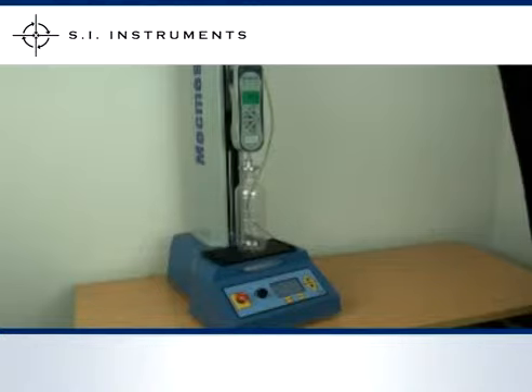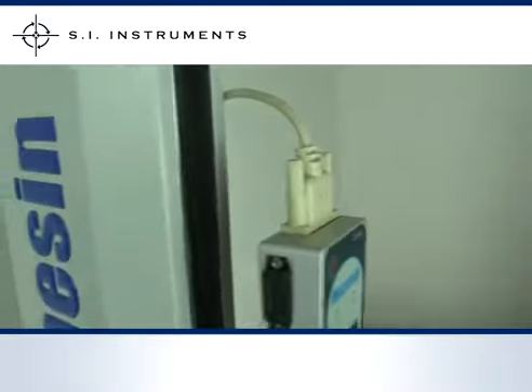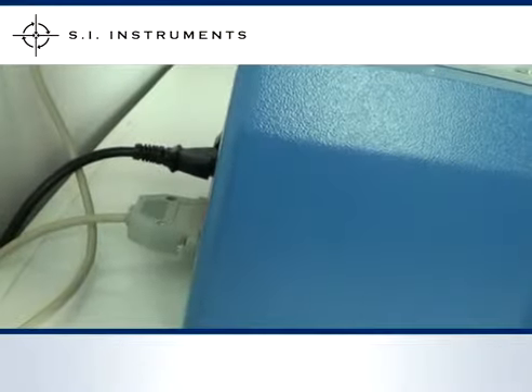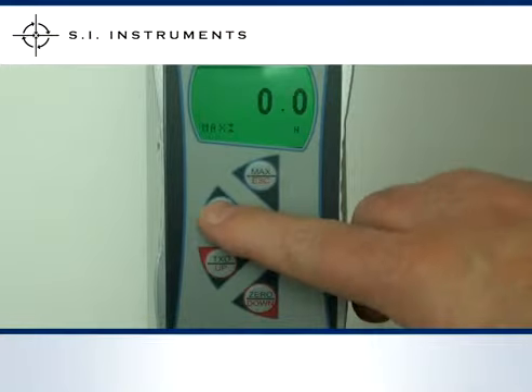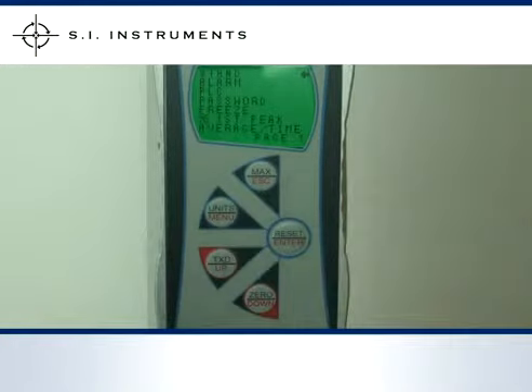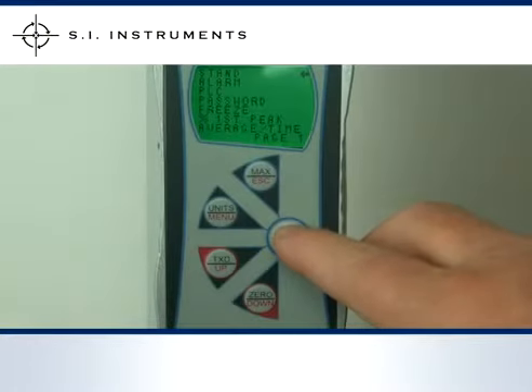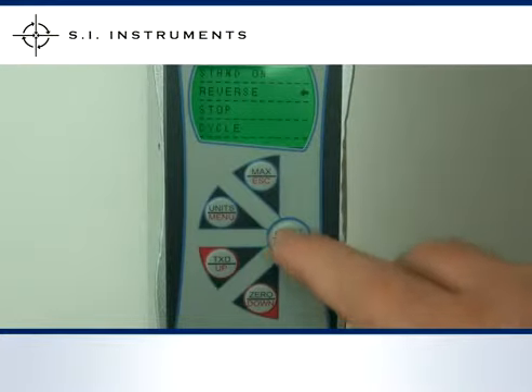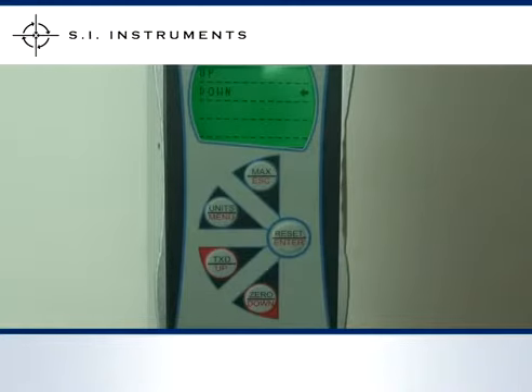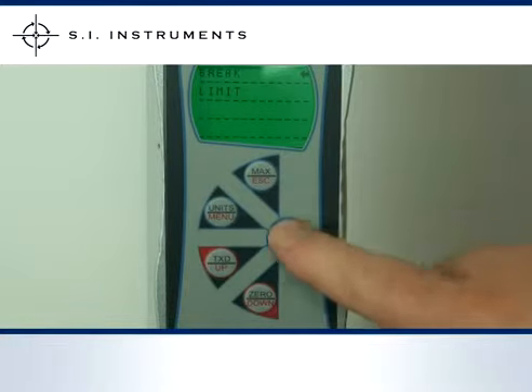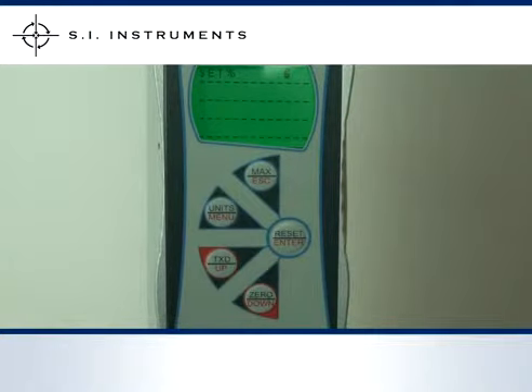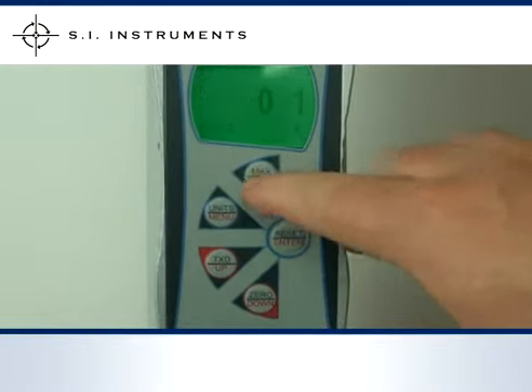In this example, we are testing the top load of a plastic bottle with the use of the Mecmesin Multitest 2.5D. The gauge is connected via the output to the test stand for the feedback signal. To set up the gauge, first select the menu, then go to Stand Control and select either Reverse, Stop or Cycle. In this case we've chosen Reverse, and for the test direction we've chosen Down. The reversing criterion, either break or limit, is in this example break. The sensitivity of the break is set to 5%. Then we press Escape to return to normal operating mode.